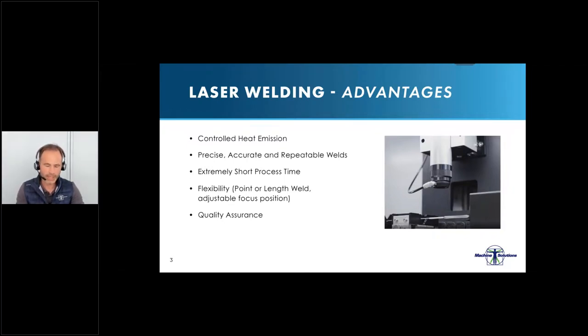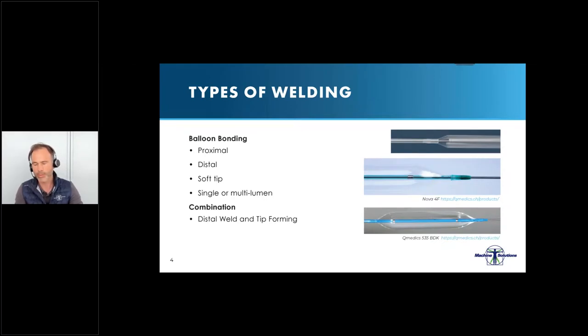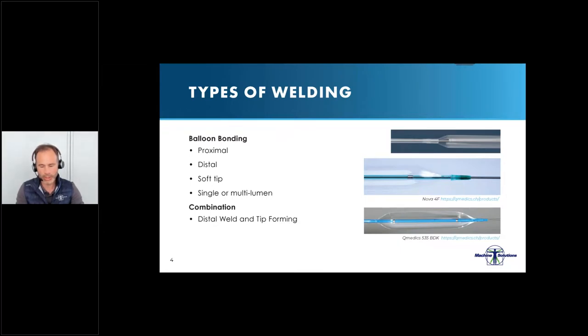The main applications for laser bonding include different types of welding. The main application is welding of the balloon to the catheter — we can weld the proximal side, the distal side, and also do the soft tip. We can do single lumen and multiple lumens. The machine gives you the capability of doing distal weld and tip forming in the same process, as well as doing tapered welds.